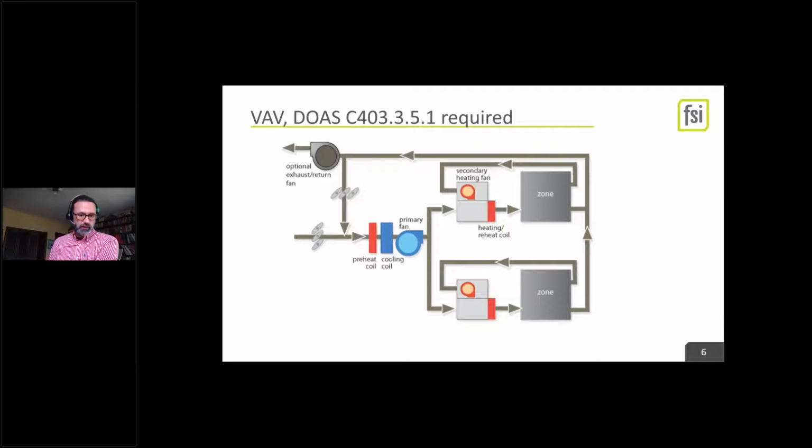You'll be reworking interior plenum spaces because you will have the ductwork supply out for ventilation if you continue to use the VAV ductwork, but you will need some secondary ductwork for the local conditioning, heating, cooling equipment to divorce them. If you don't like that, there is an alternative.